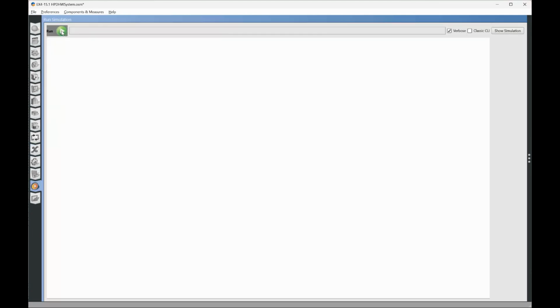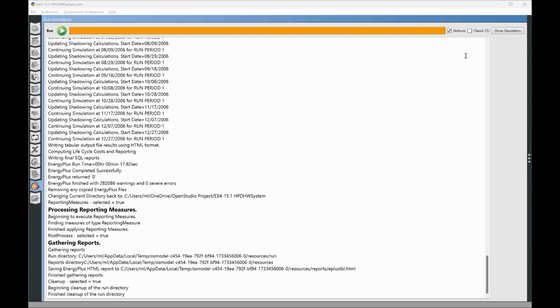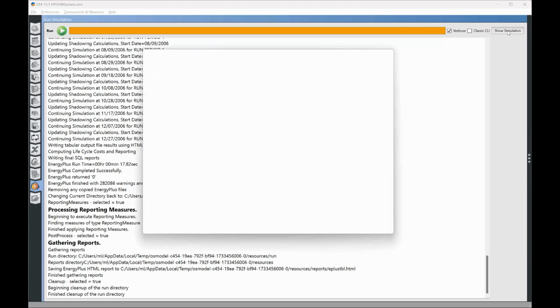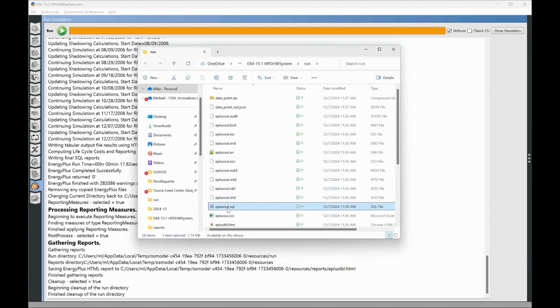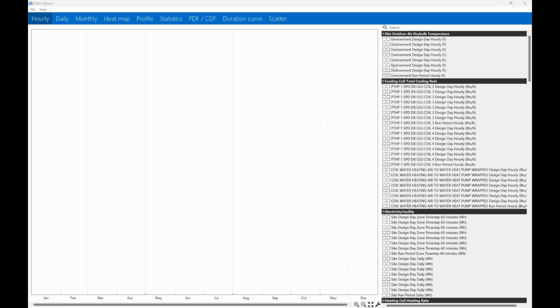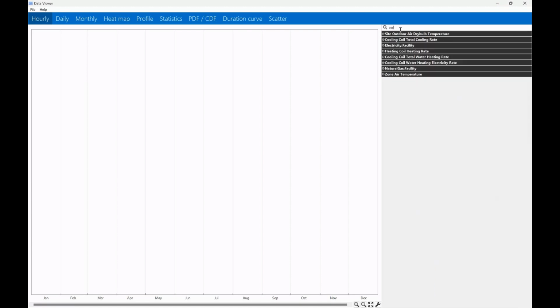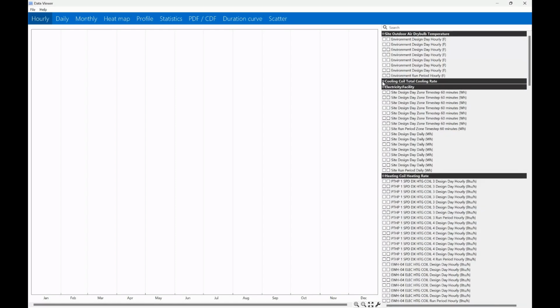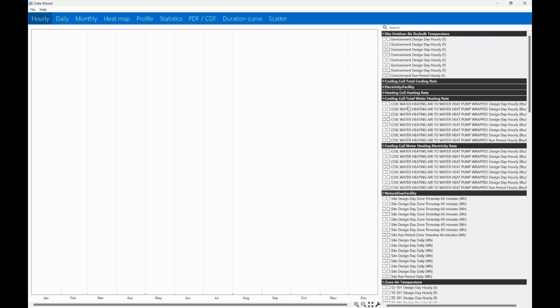So we'll go ahead and run the model again, and it has completed successfully. Let's take a look at that trend data. We'll go to Show Simulation, and then we can select the SQL file. We'll just display it in IP units. Let's search for cooling coil. Let's go to cooling coil total water heating rate, and we're going to select the run period.